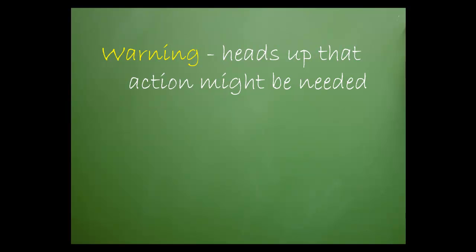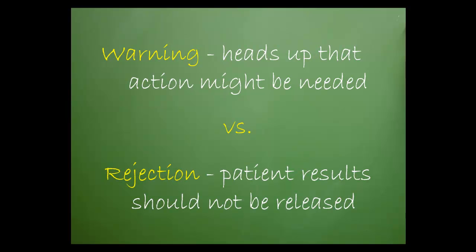Think of a warning rule violation as a heads up that action may be needed. However, in the case of a rule rejection, patient results should not be released.